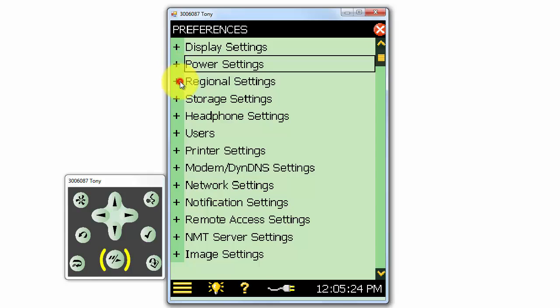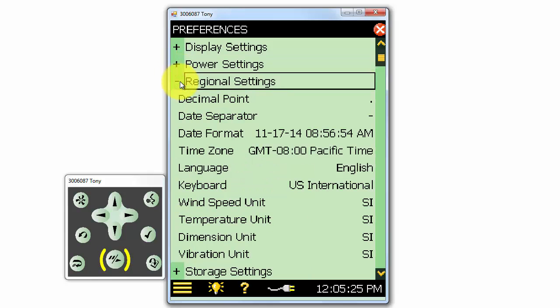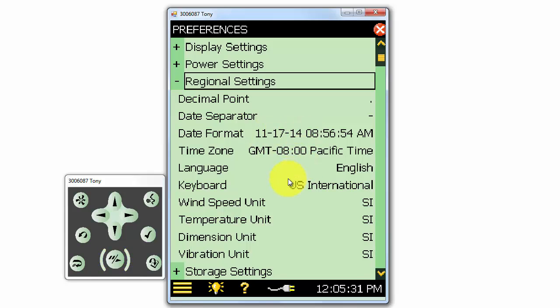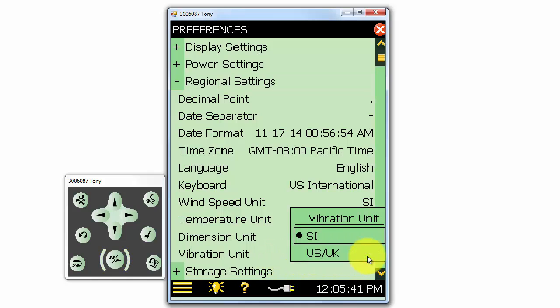Under regional settings, we can select our time zone, what date format we would like to use on the meter, as well as what type of unit we would like to use for different parameters. For example, if we're measuring vibration with an accelerometer, we can select between SI and US-UK units to look at values in either meters per second squared or Gs.